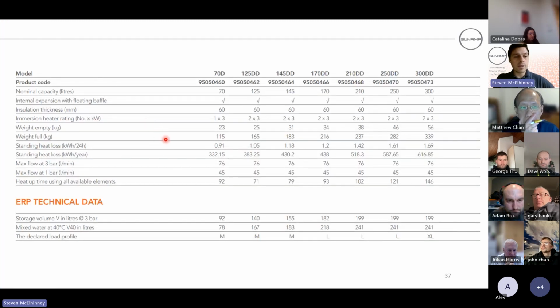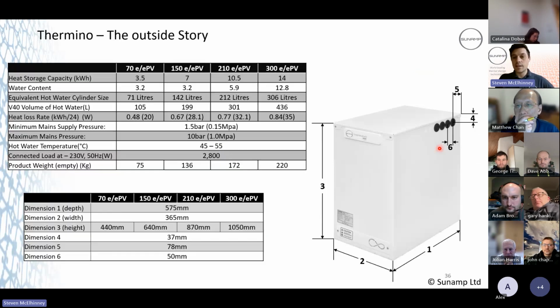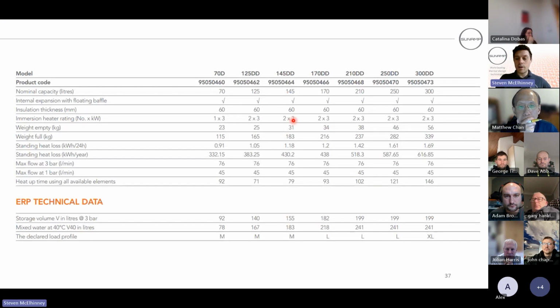And if you go way up to the 300 litre, it's 1.69 kilowatt hours over a 24-hour period. And we are miles less than a kilowatt hour. So our units are much better thermal insulators than a cylinder ever will be, and we can prove that here.